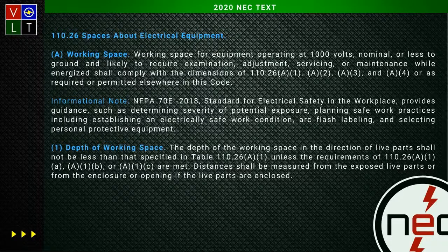Right below that, there's an informational note that tells you to go see 70E. The reason that's in there is we've added a lot of informational notes all through Article 110 that reference going back to 70E. It can be for dealing around working space, your arc flash warning to tie in with 70E, or your available incident energy or short circuit current. 110.24 and 110.16 all have this reference to go check 70E out.